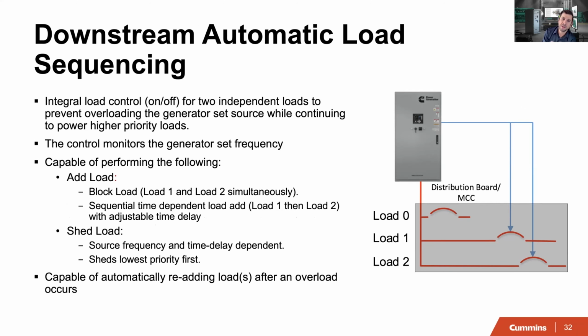There is also built-in automatic, which is unique in the industry, by the way. We have also a patent in this. There's downstream automatic load sequencing, where the transfer switch control looks at the frequency of the generator, and if it sees that they're struggling, which is the frequency, is a real indication of a struggling generator set, not the kW. It manages up to 2 loads downstream with that transfer switch. It can automatically add those, block load add them, and shed them if there is an overload happening on the generator.